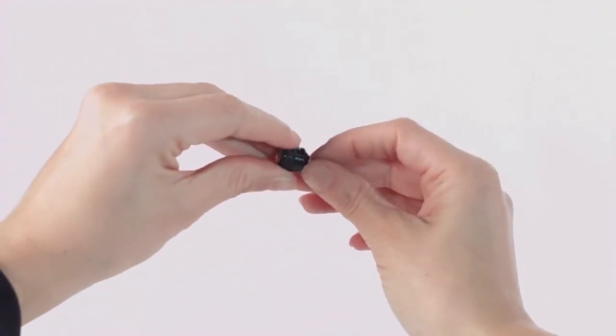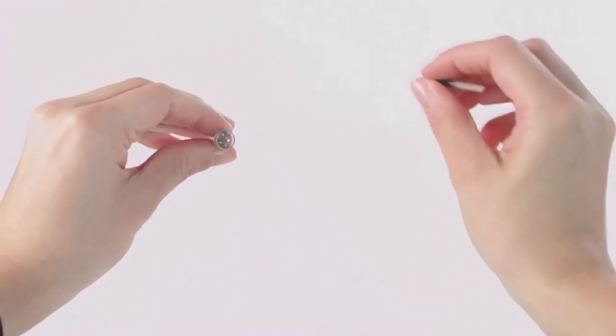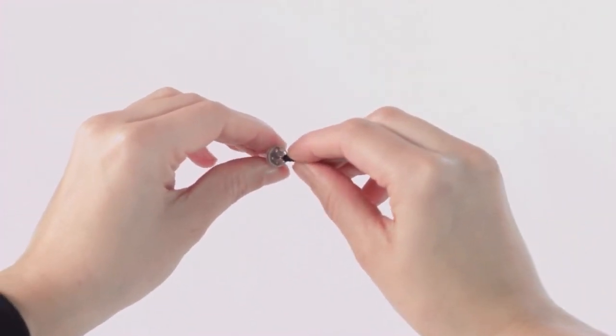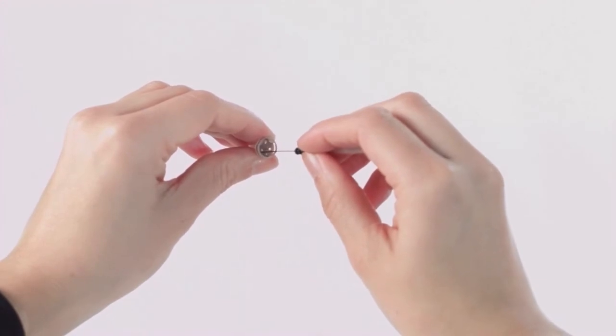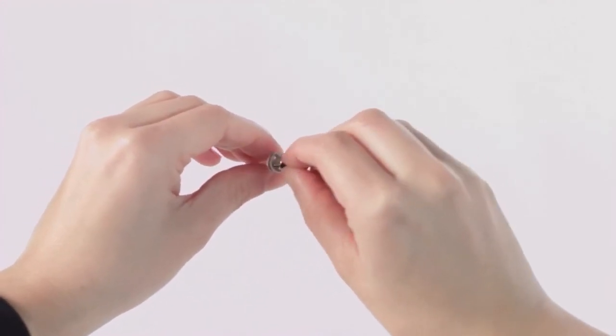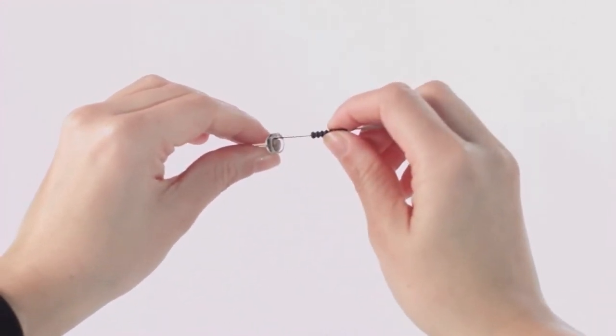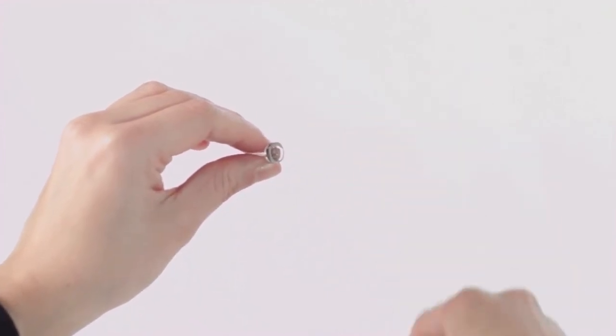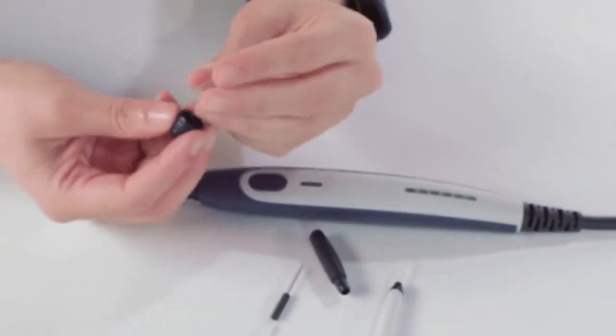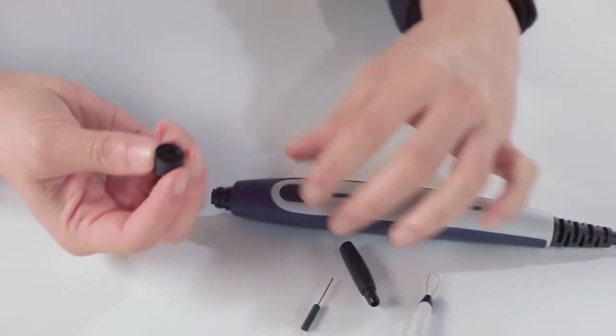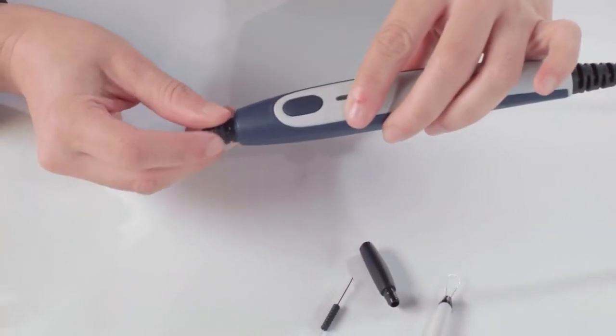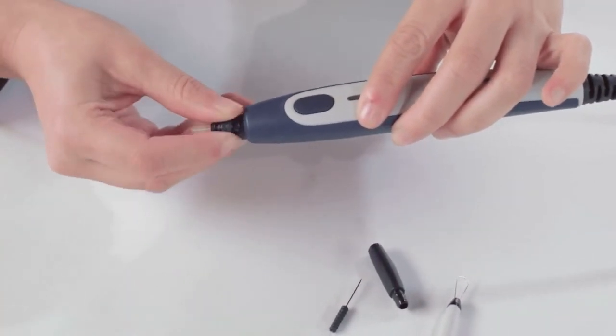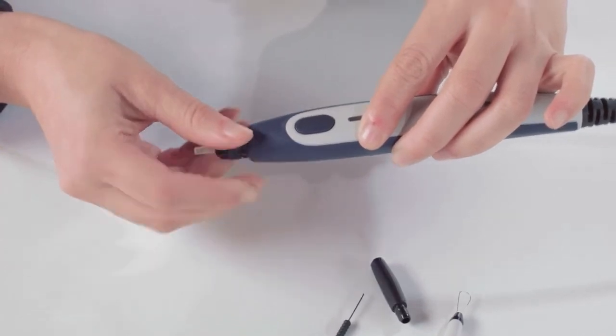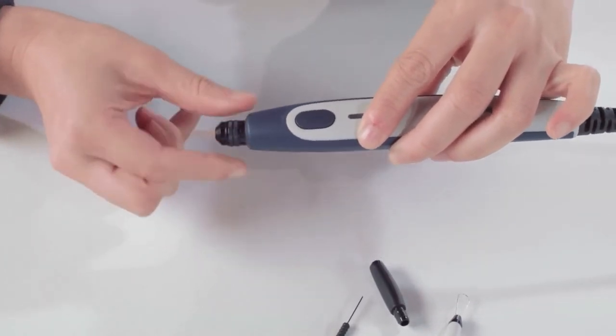Take the plastic probe tip out of the probe and take the cleaning tool apart to find the thin brush and thin rigid plastic cord. Use the plastic cord or brush to push debris out of the probe tip. Always enter the probe tip from the rear to avoid accumulation of debris inside the vents. Place the probe tip back, making sure that it is inserted appropriately onto the probe. The force of tightening the cap will tighten the screw sufficiently.